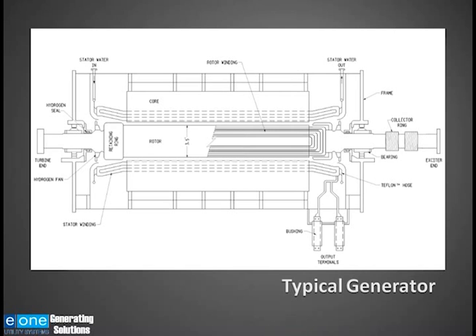One of the areas that is very difficult to seal, or where it's difficult to seal the hydrogen in the generator, is the rotating field or the rotor. You can see the hydrogen seals on each end of this generator. They're used to keep the hydrogen from leaking out. You will also note the hydrogen fans on each end of this generator rotor, which are used to circulate the hydrogen. Some generators have 2 fans. Some have 1 fan. Some will have a blower assembly at the end of the rotor. These fans or blowers will create a high pressure and low pressure, which we will discuss later.